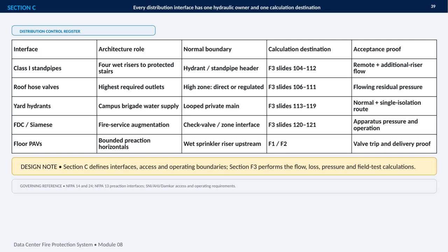This section establishes a simple but important rule for the distribution interfaces. Every interface has one hydraulic owner and one calculation destination. That separation keeps responsibilities clear and prevents the design from treating boundaries as shared or ambiguous. The register identifies 5 interfaces. Class 1 standpipes serve 4 wet risers in protected stairs, with their performance calculated in F3 and accepted through remote and additional riser flow testing.